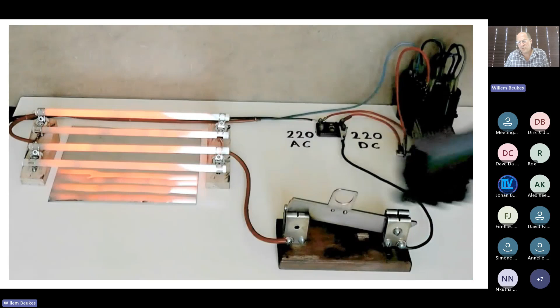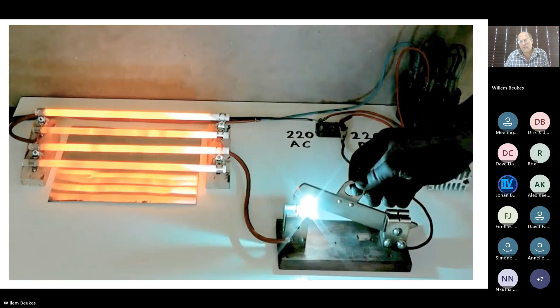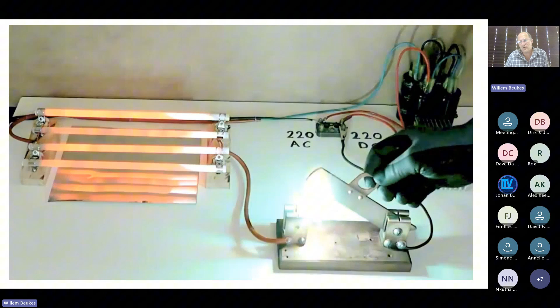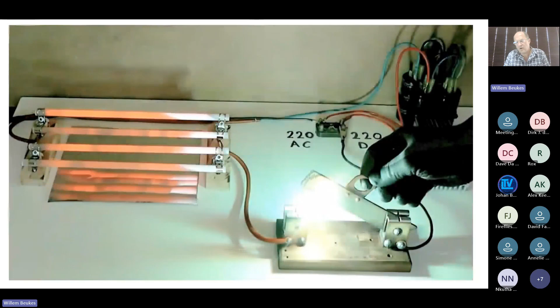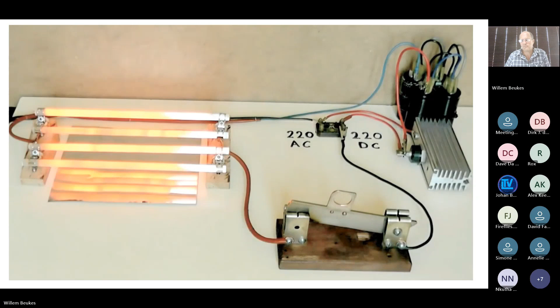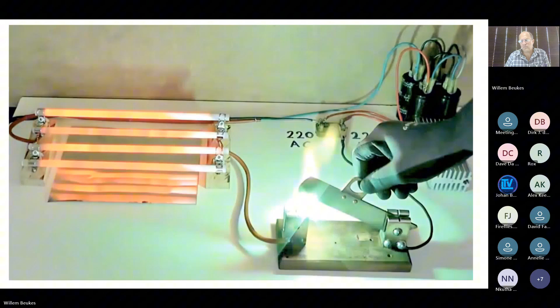And it's that arc that contributes to the combustibility of the equipment, and can then cause combustion of any other material on the roof. There are two components in this arc: the electrical component and also a heat component. With some other panels, depending on what type of panel you're using, you have some polymer panels as well. That's also combustible, where the material itself is combustible. I'm just going to show this video as an example of that.